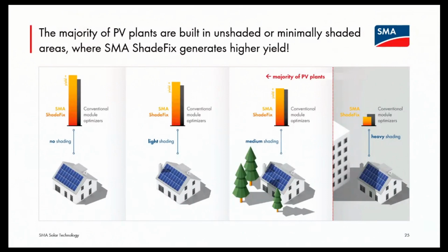Back then we looked into a study done by a university in Denmark, comparing string inverters with module-level electronic systems. String inverter systems in general had higher yields, or at least equal yields, compared with module-level electronics systems. Even in slightly to medium shaded situations, PV systems with string inverters performed better. In particular, we reviewed our performance with ShadeFix, and that came out very well. We found that only for very heavily shaded systems, shown here on the right, there's a slight plus in total annual yield compared with a string inverter system.